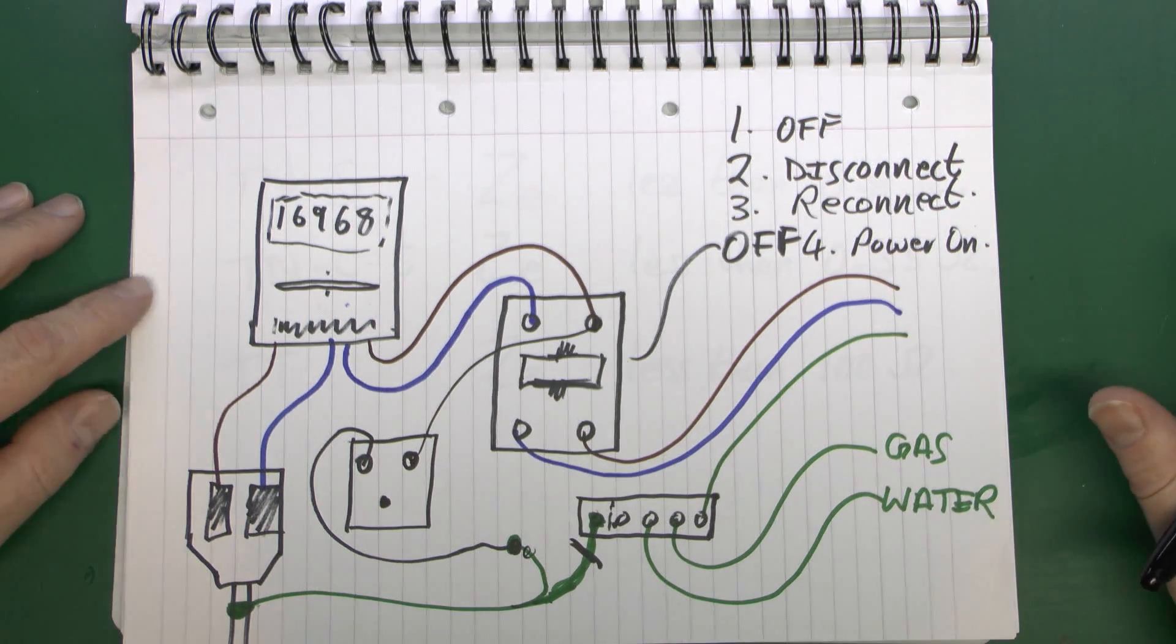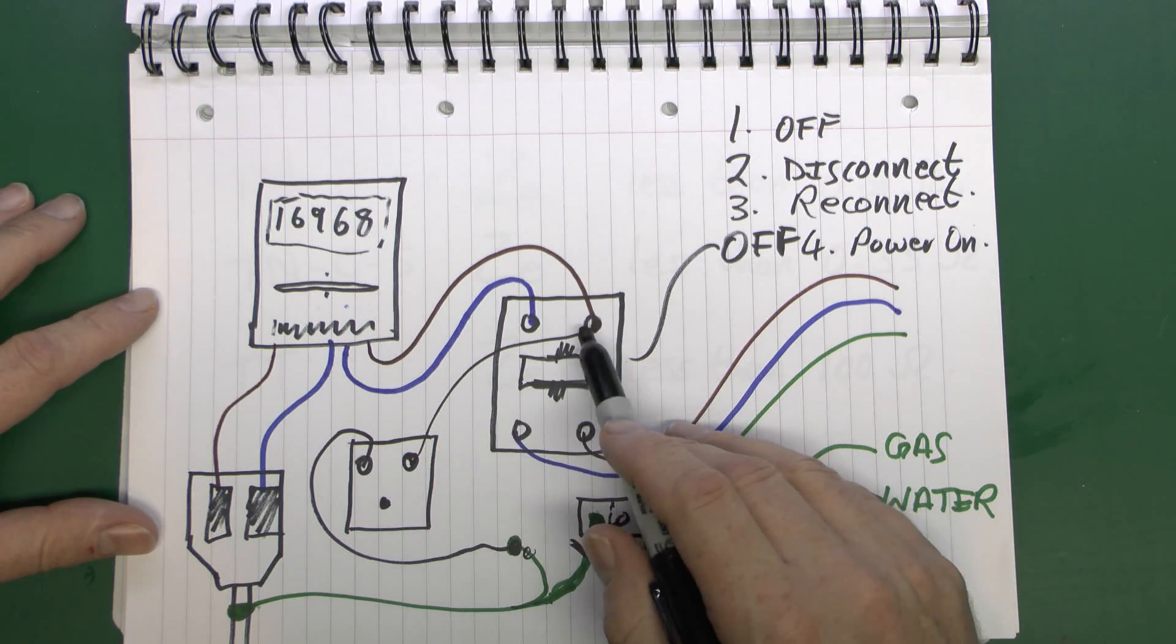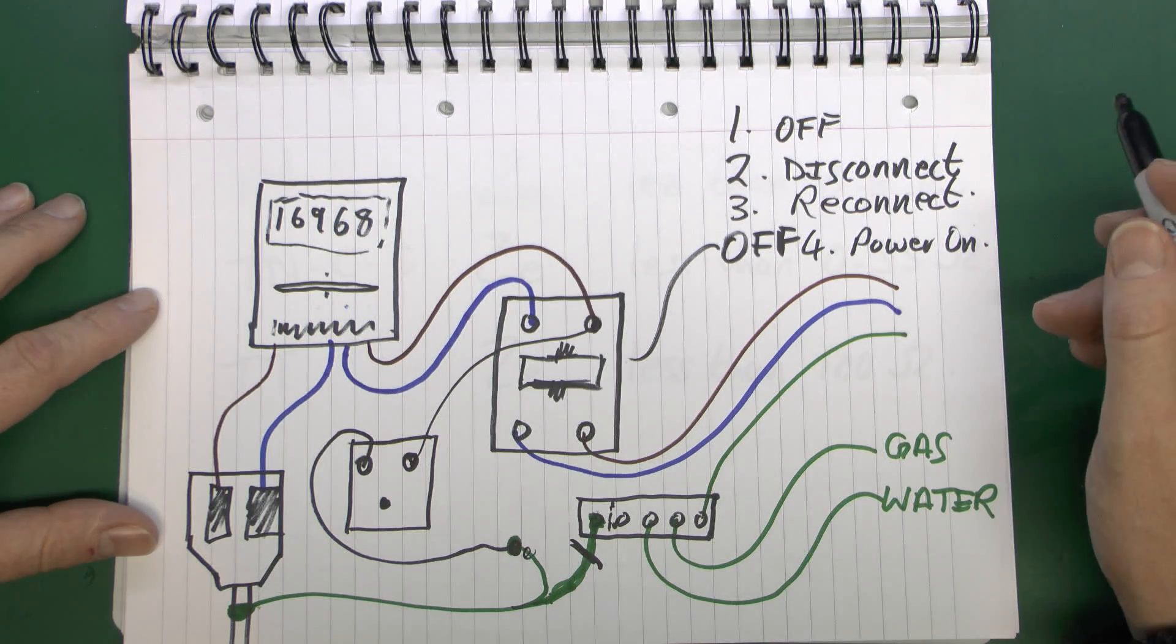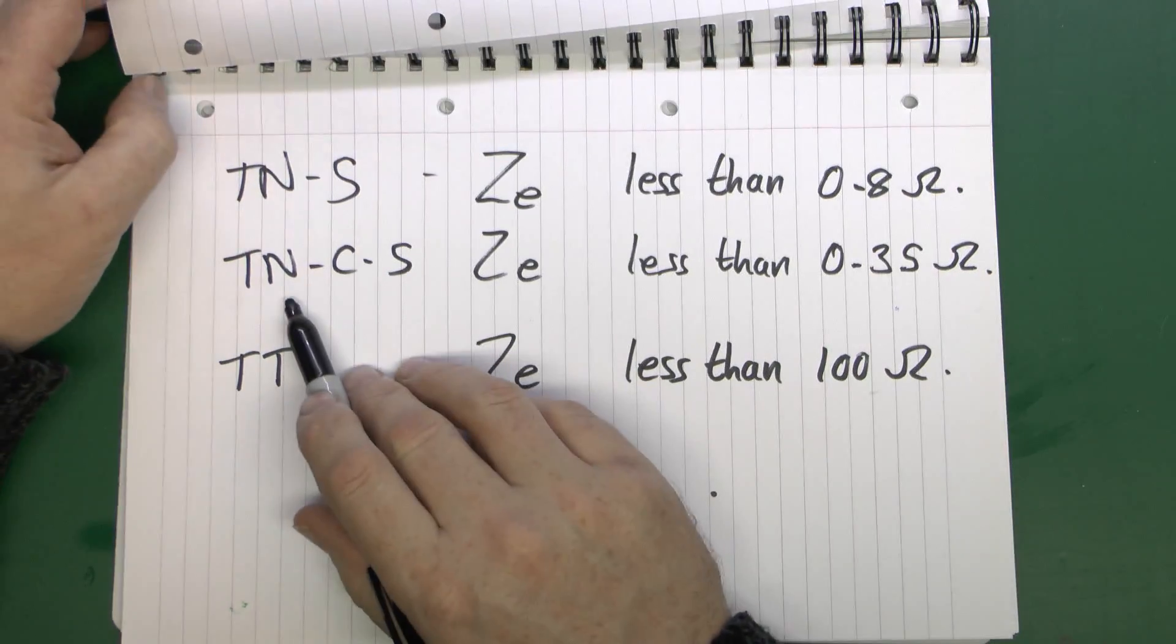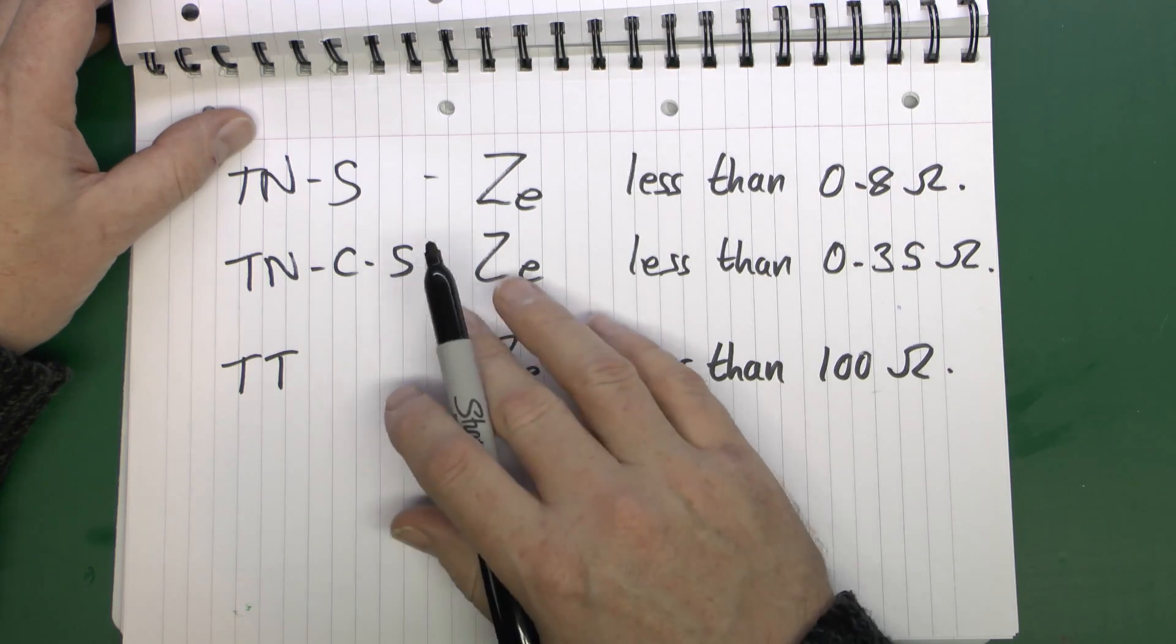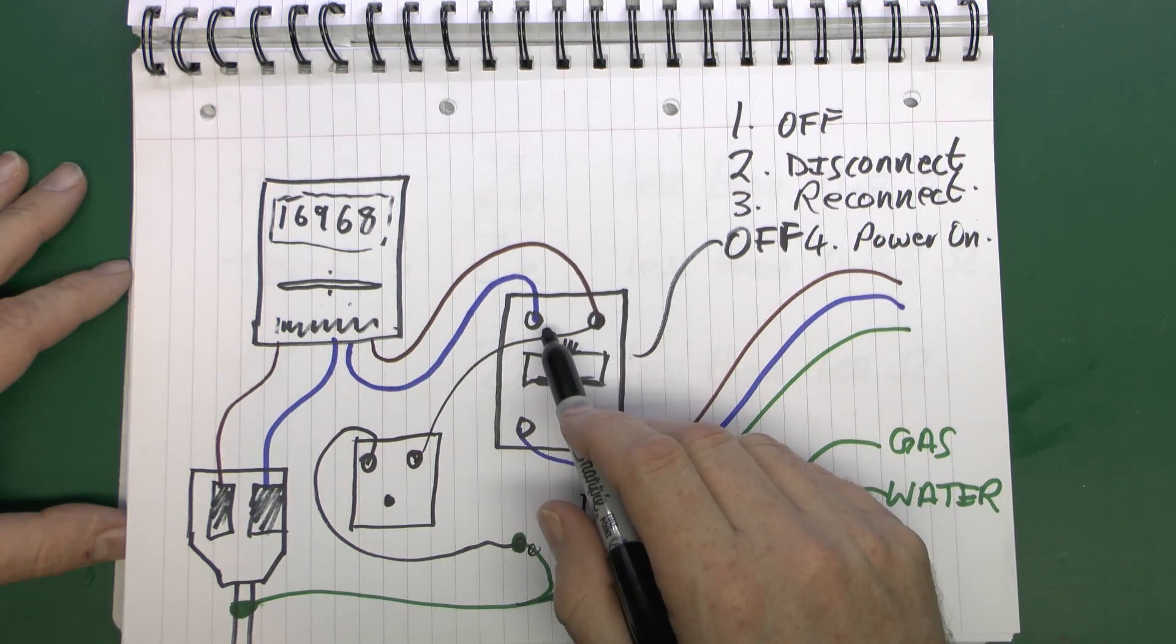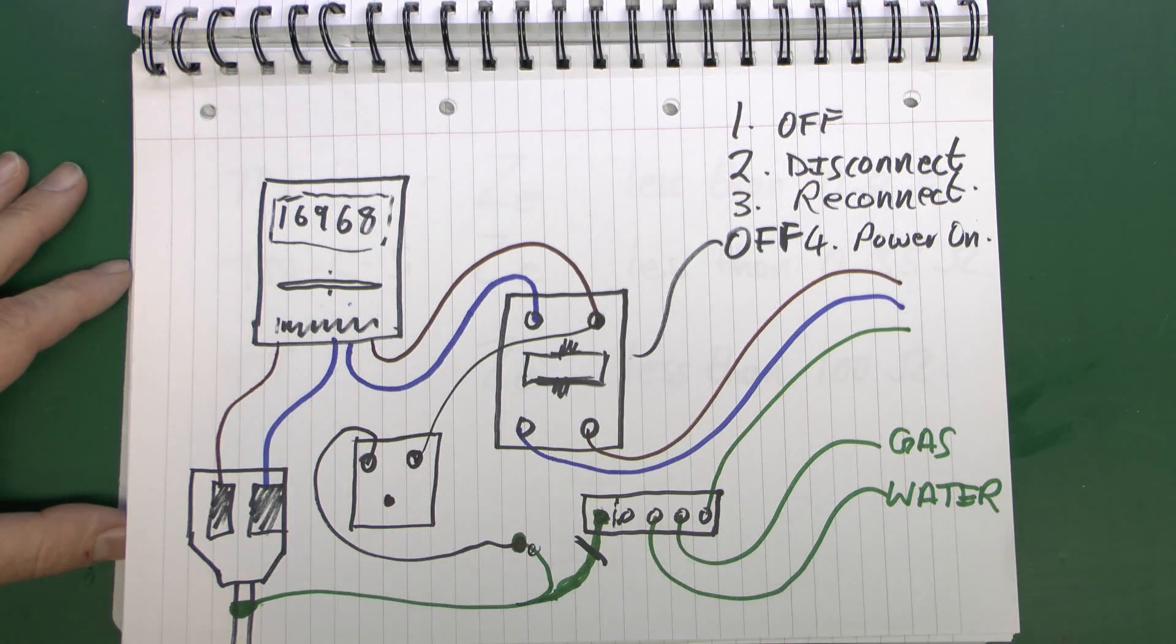Now as well as the fault current between line and earth, you do also need to consider the fault current which could occur if there was a fault between line and neutral. And to test that it's exactly the same procedure, the same device is used, except you would test between the line and rather than the earth you would just test between the neutral of the incoming supply. Now depending on what kind of supply you have, this could actually be the same value as you get for the one for the earth. So for example on the TNCS supply, the cable you're testing is actually the same one because it's the neutral and earth combined, so in that case you would expect the fault current to be exactly the same. However on a TNS system as we've got here, then the actual loop impedance between line and neutral is typically going to be quite a lot less than it would be between line and earth, and then the current will actually be considerably higher. And definitely on a TT system it will be considerably higher there.